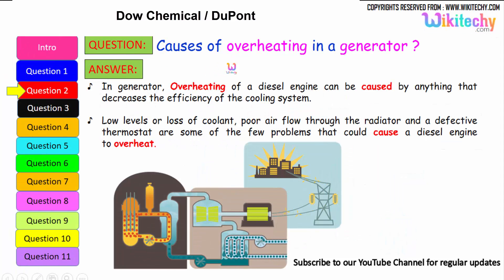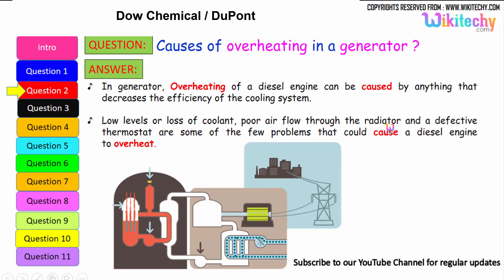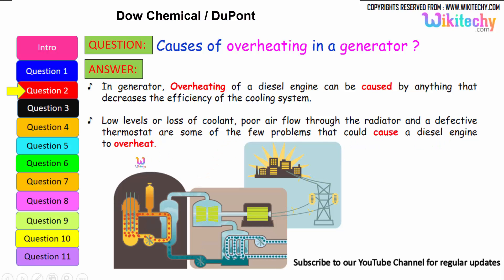Let us move on to the next question: causes of overheating in a generator. Overheating of a diesel engine can be caused by anything that decreases the efficiency of the cooling system. It can be due to loss of coolant or low coolant levels, poor airflow through the radiators, and a defective thermostat — some of the problems that could cause a diesel engine or generator to overheat.